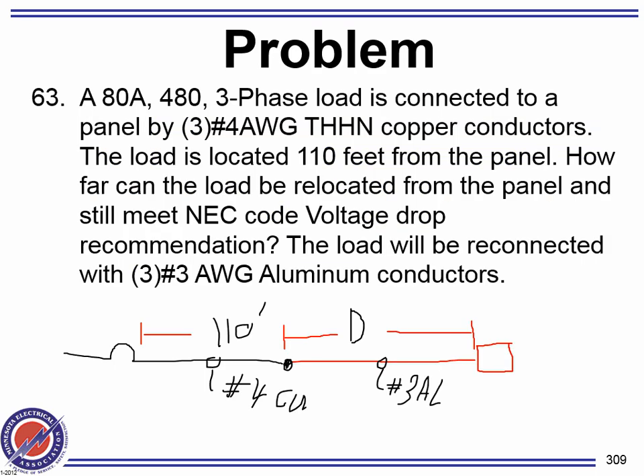All right. This was seen on the test. We have an 80 amp load right here. The voltage is 480. It's 3-phase. It's wired with number 4 copper. Can you guys see that? One section. The load is located 110 feet away from the panel, like you see it right here. How far can the load be relocated from the panel and still meet the NEC code book requirement, a recommendation? The load will be reconnected using, because we're knuckleheads, number three aluminum. Does that make sense?